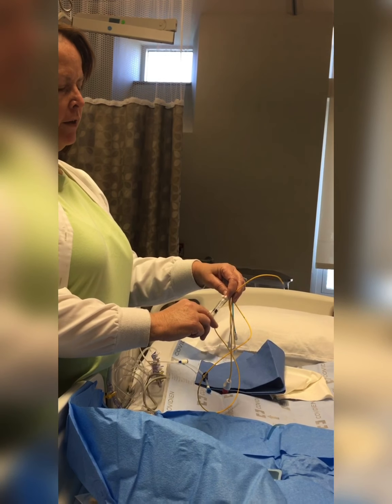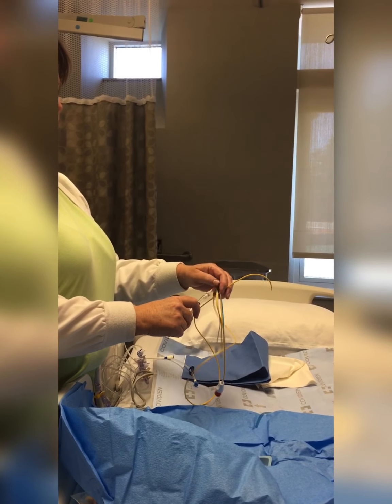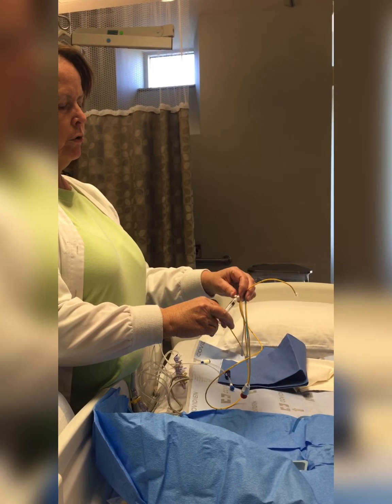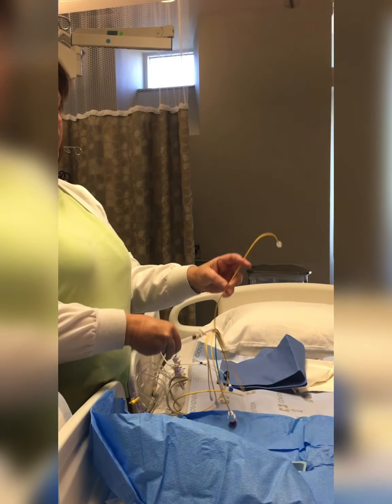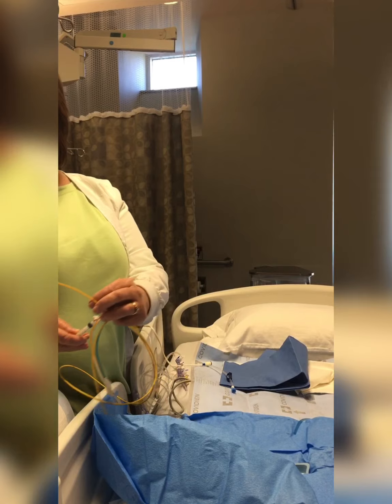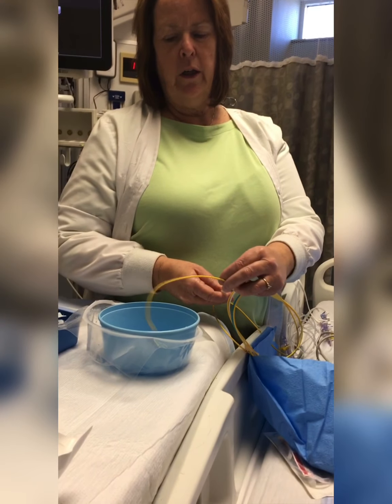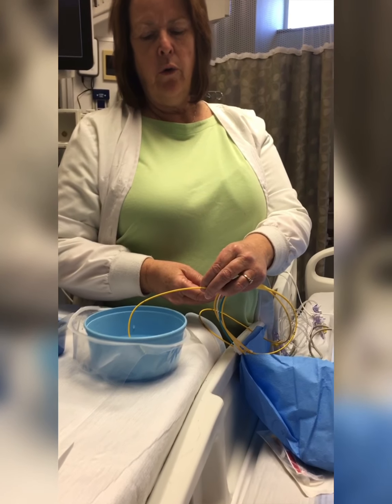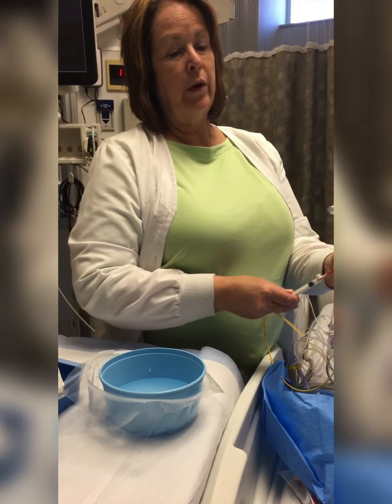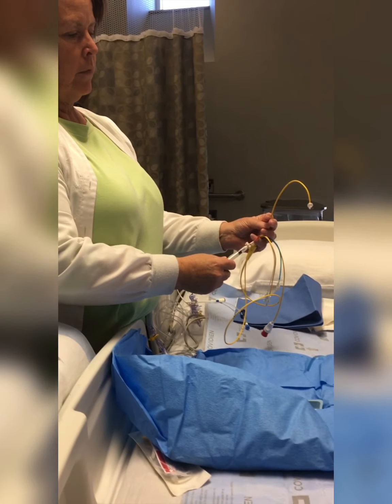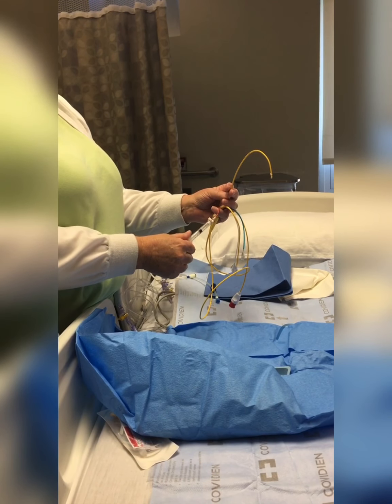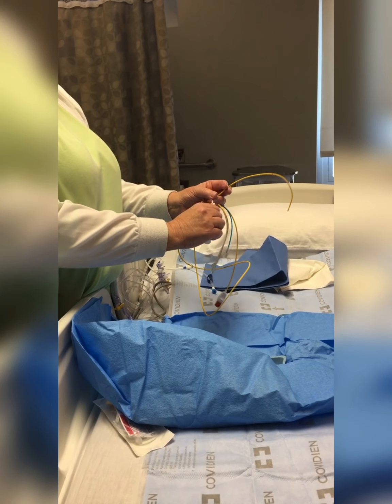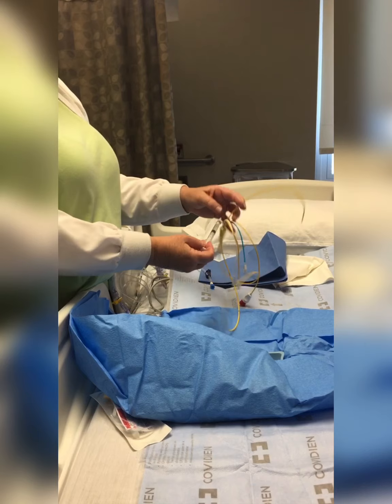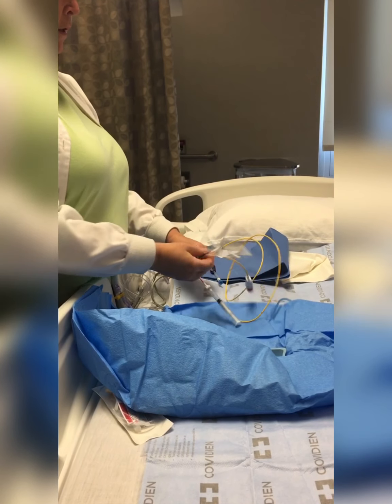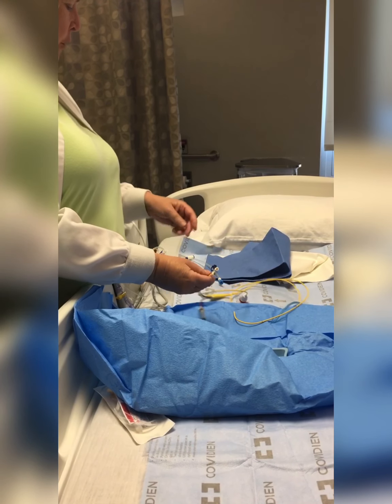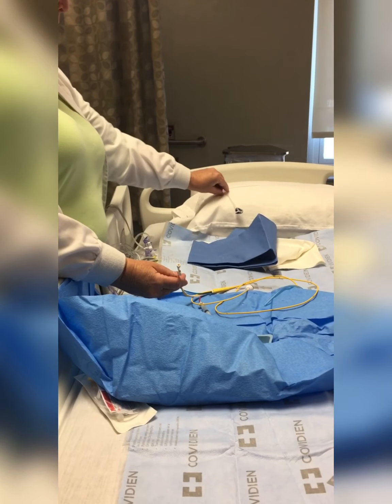So you have to check that balloon before the doctor inserts it. One of the things you can do is inject it here, and you want to make sure there's no leak. So you would have the doctor put the balloon in the saline to make sure no air bubbles come out of there, which would show a leak. So then, now that I have the syringe on there, I'm going to press lock again. So we're going to go to these other things to hook up our tubing. This is in our patient.